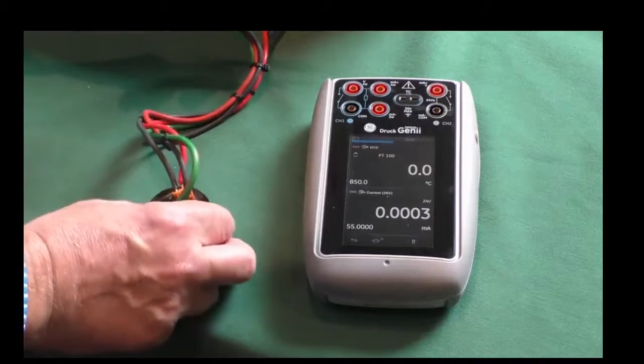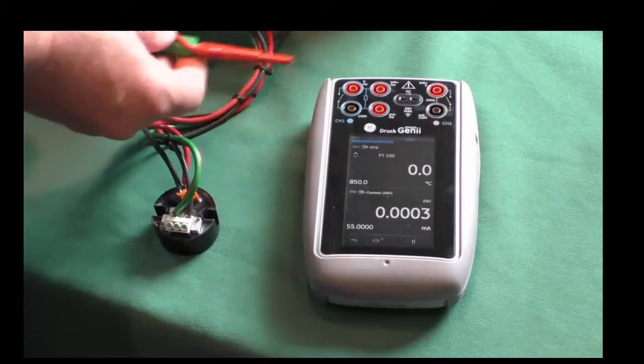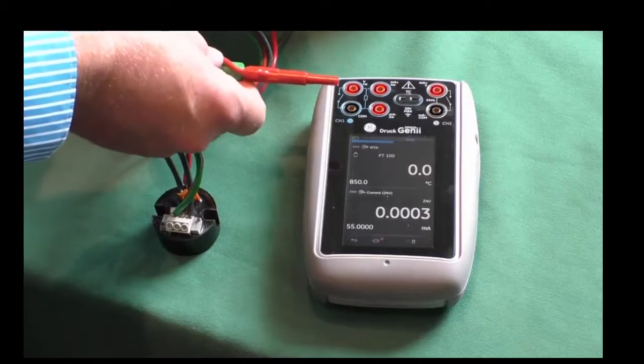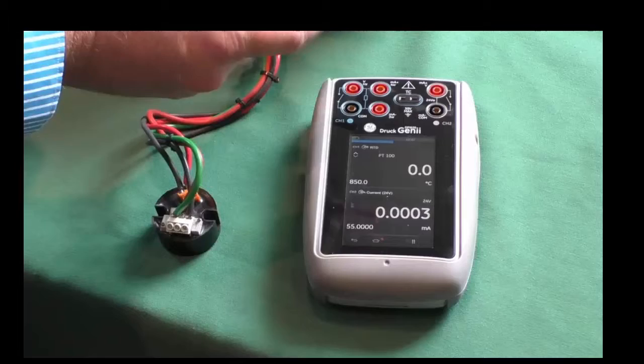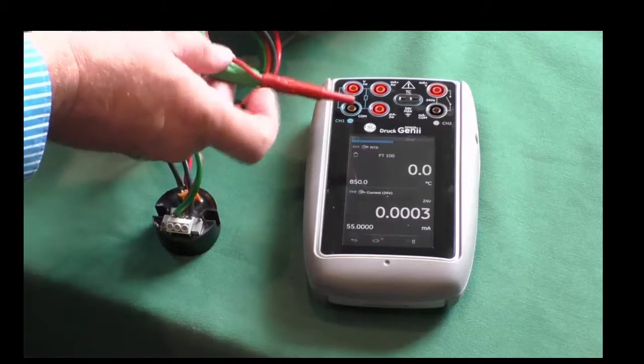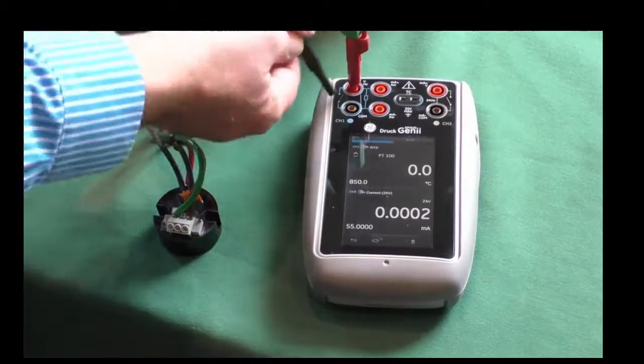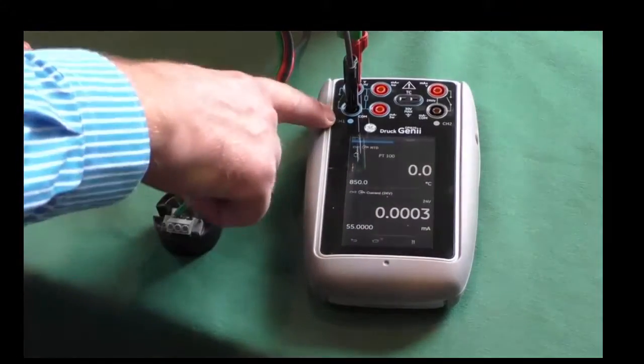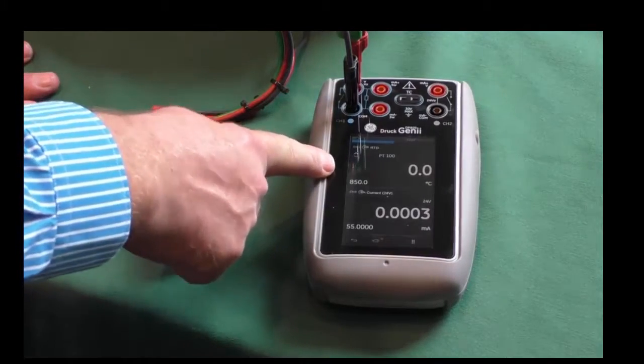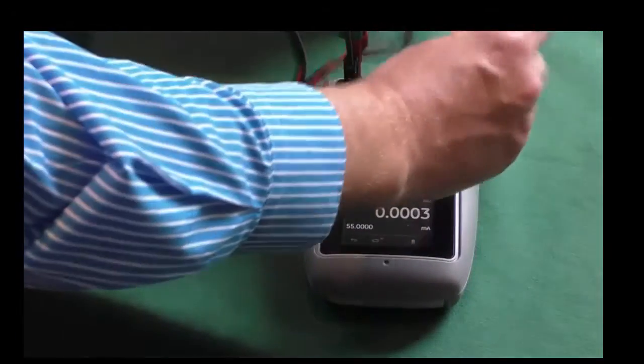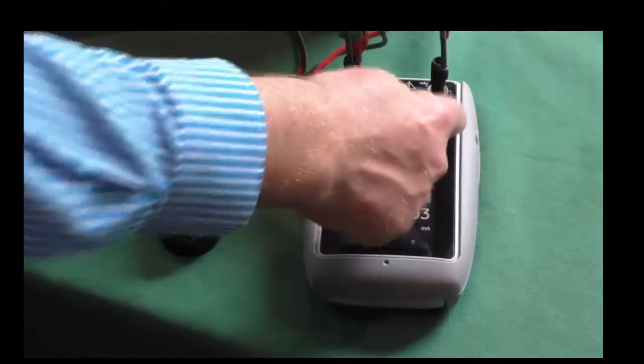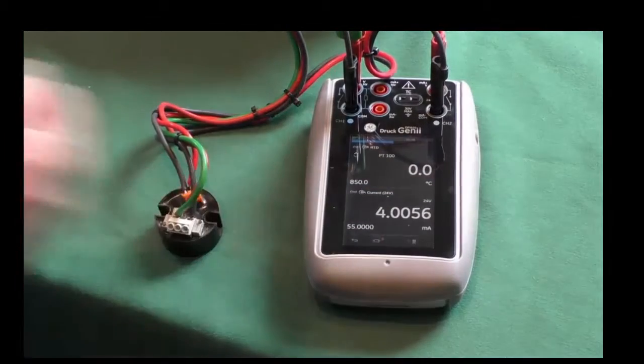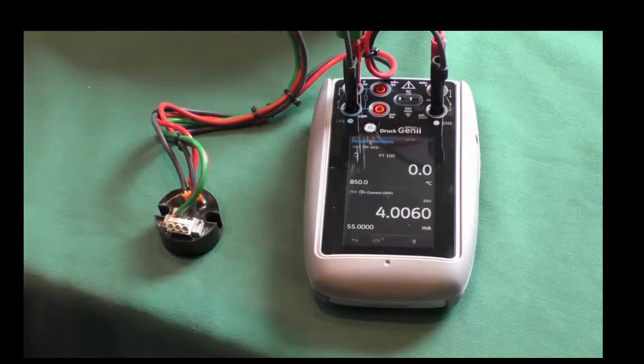So here I have a rather old RTD transmitter. It's a 3-wire. When we're actually sourcing or simulating, we don't need to connect all 3 wires independently. So what I've done is I've joined the compensation wires together there. We make a simple connection on this side. So it doesn't matter which way around I do this, it's a resistance. So that's channel 1. So if we look on here, channel 1 is degrees C. Now it's a transmitter, so as you remember before, we've got 24 volt supply on channel 2. Connect that in, and straight away 0 degrees C is 4 milliamps. So this is a PT100, 0 to 100 degrees C. So now what we're going to do to calibrate this transmitter and set it up will be to simulate the temperatures. Now there's a number of ways that we can do that.